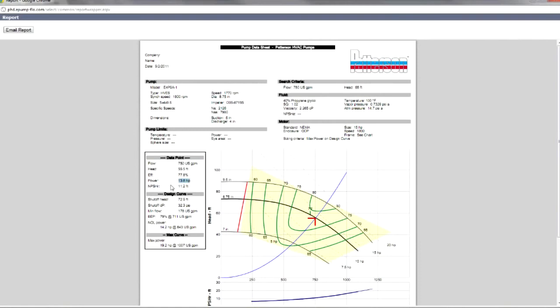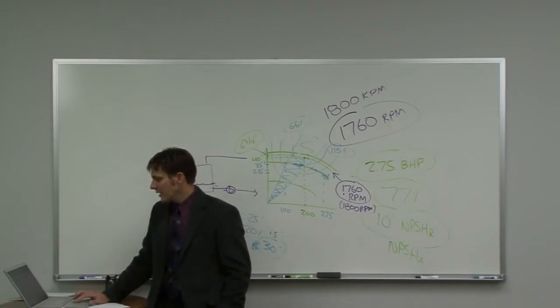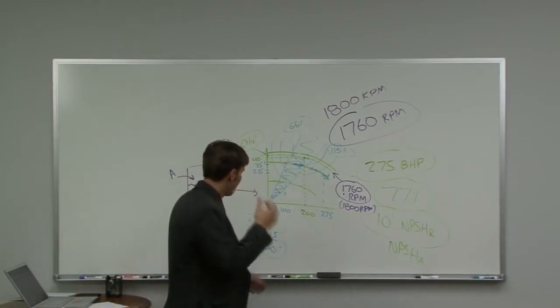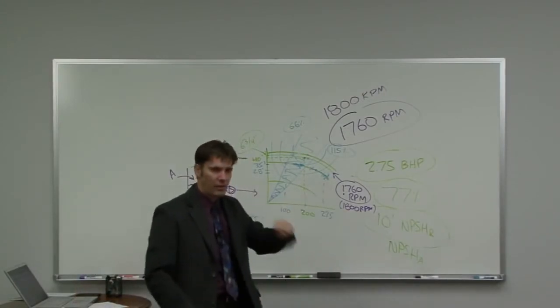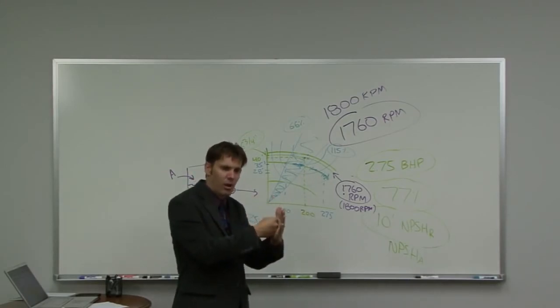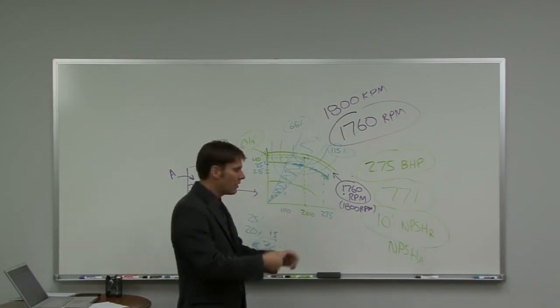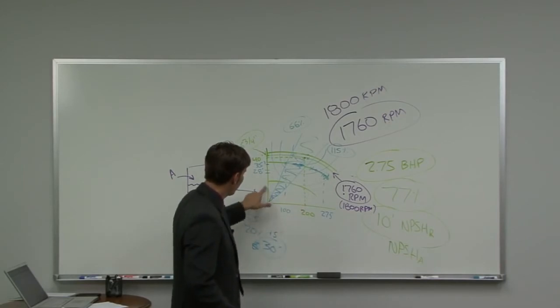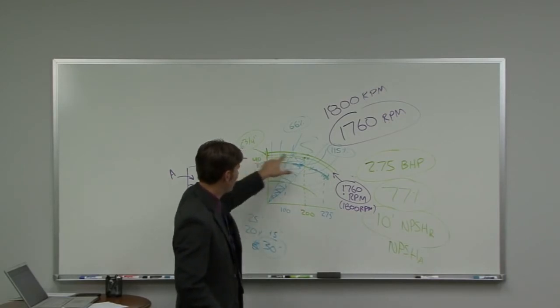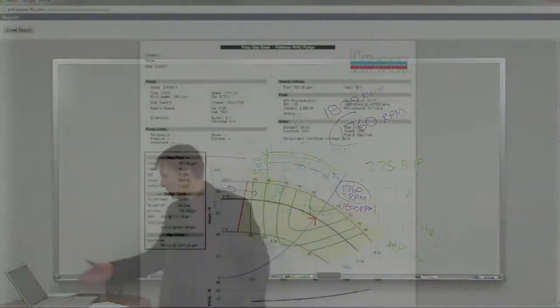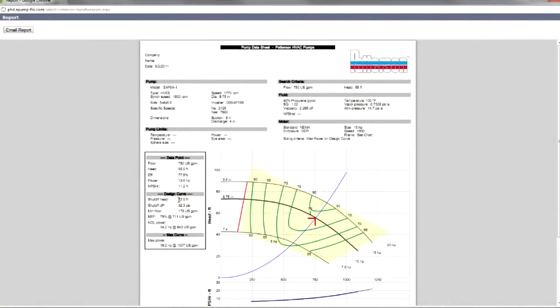So we are at 13.8 brake horsepower. Our efficiency is 77.8 at that point. Our NPSHR, instead of trying to guess based on the lines, it tells us it's 11.2 feet. It tells us what our shutoff head is. The shutoff head is that head pressure, back to this curve, if I were to close the discharge valve on my pump and have zero flow. It's operating at full speed. So zero flow on this curve at full speed. I know what my impeller trim is. That's my shutoff head. So my shutoff head would be 72.9 feet.